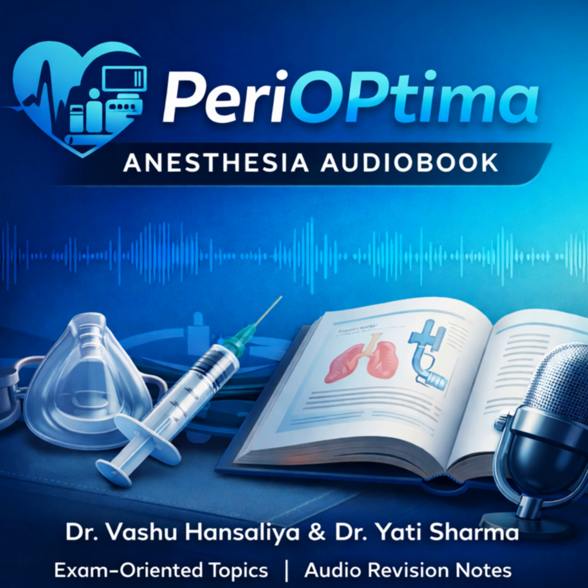For ETO and dry heat, we use the spores of Bacillus subtilis, or, more recently, Bacillus atrophaeus. And the good news is we don't always have to wait 2 days for the culture to grow anymore. Modern biological indicators have a rapid readout system that can detect a specific enzyme from the living spores, giving you a result in just 1 to 3 hours.